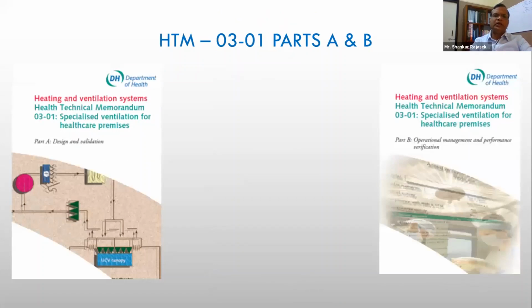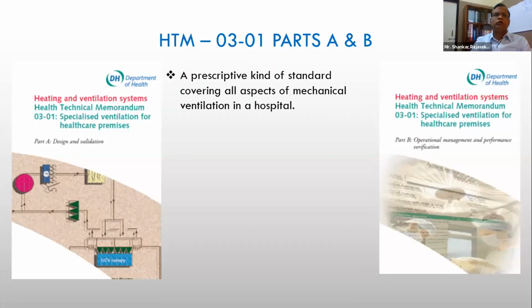The next one, which is typically my personal choice, is the standard called HTM 03-01 parts A and B. HTM is the Health Technical Memorandum of the UK. The earlier one was from ASHRAE in the US; this one is from the UK. This is one which really gets down to the details. The HTM 03-01 is exclusively for HVAC systems, and specialized ventilation systems are covered in a large portion. Parts A and B put together are almost 200 pages of in-depth information.